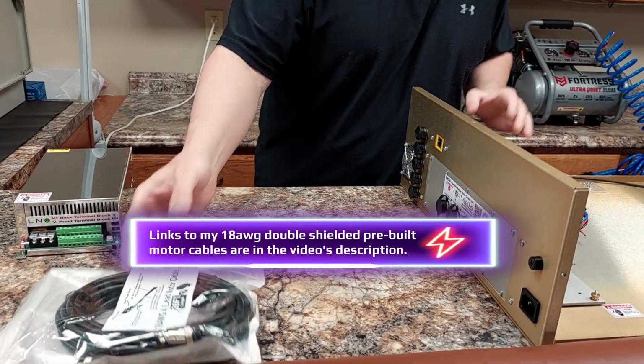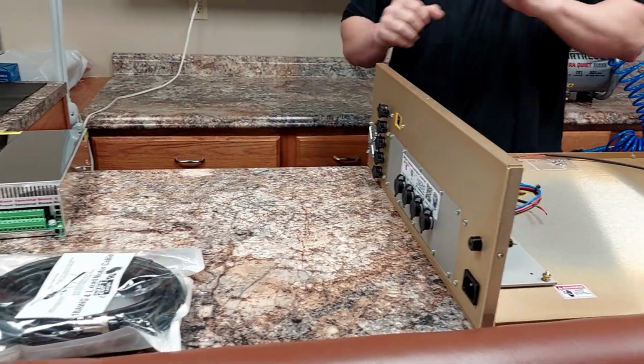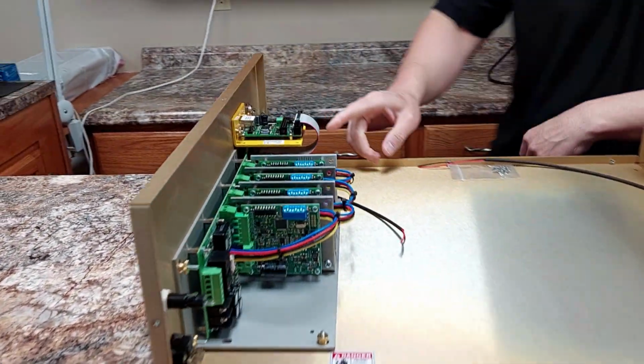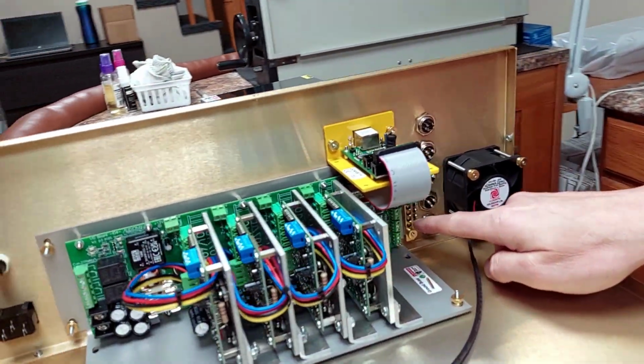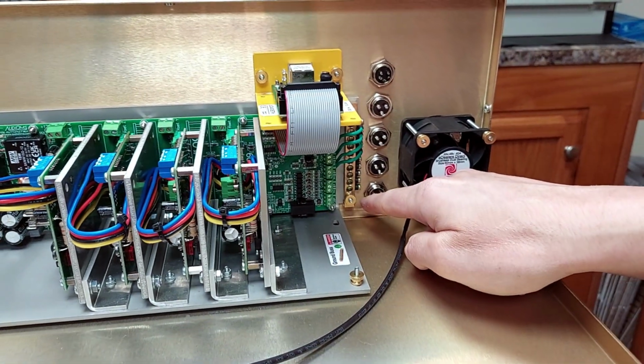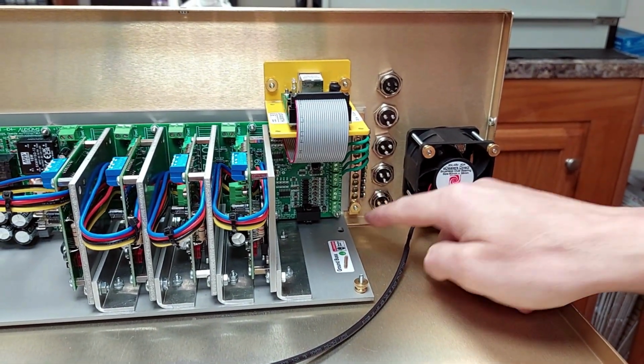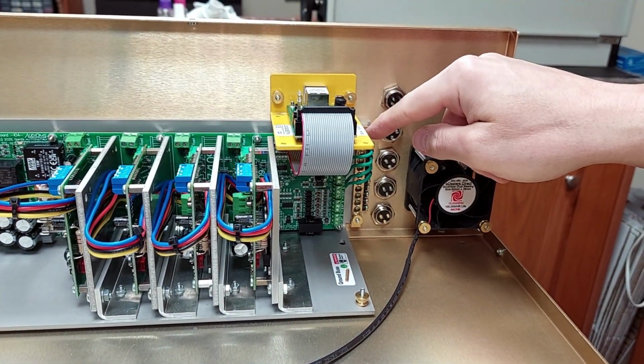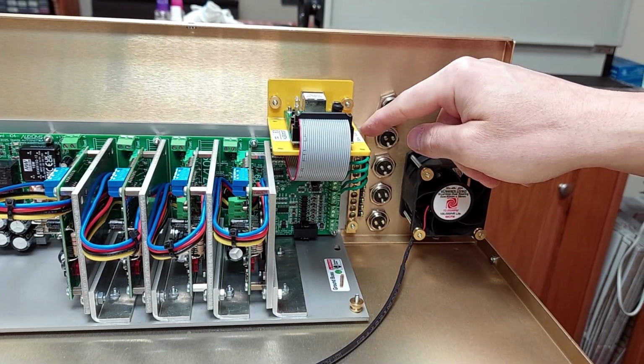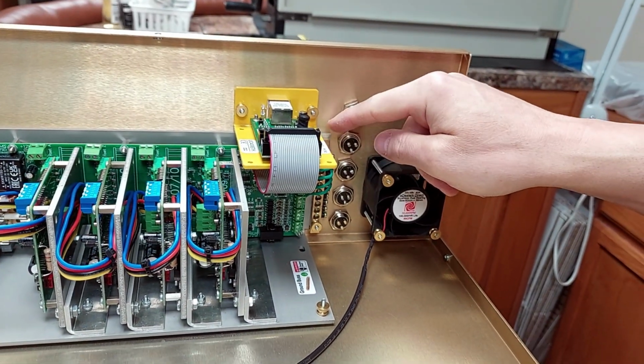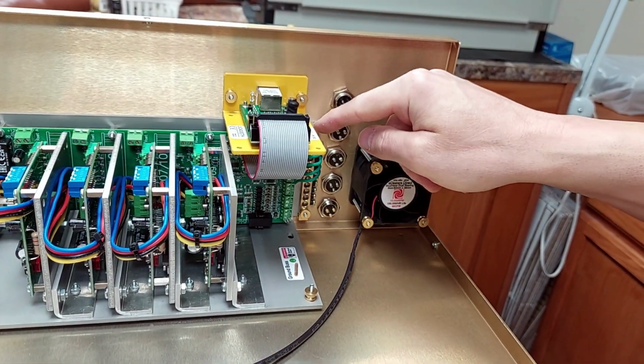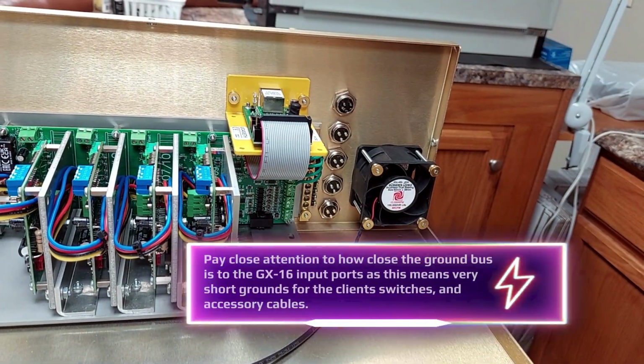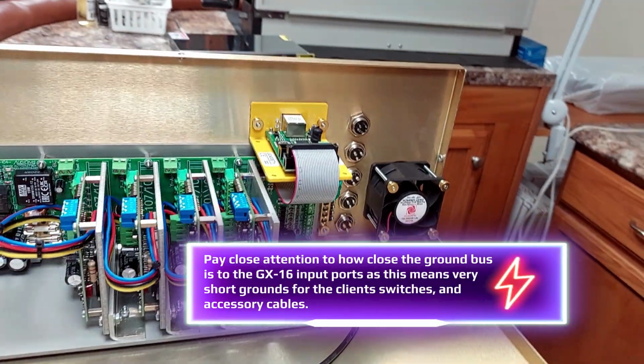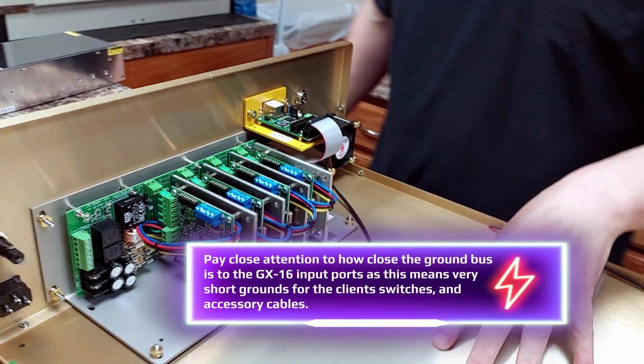Now, to make sure grounding is done properly, because this is something that comes up all the time, he'll come over here, and when he plugs in his motor cables, there is his ground bus. And by terms of actual conduction, when those screws go through and mount the drive, naturally, those screws are metal, they're conductive right to the ground bus, and that grounds the entire chassis. So it's all done. All bases have been covered.